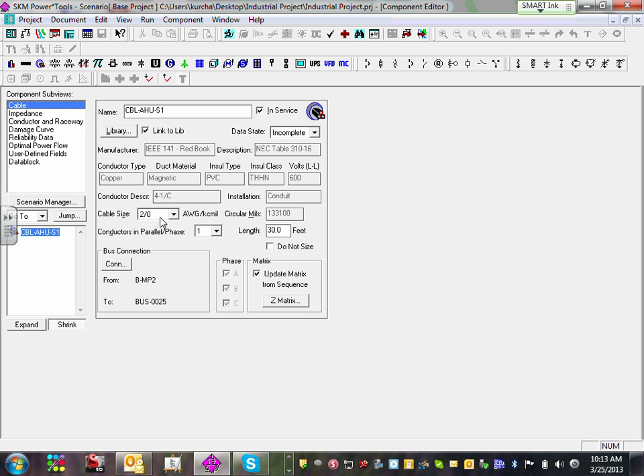Let's go size the conductor for 600 amp. So if I have my conductor, my horsepower is 60 horsepower, the voltage is 480, and I need the conductor wire size, it's number 4. Does that sound familiar? Number 4. Anybody look at their schedule? So I need to change this one to what? For this, number 4.